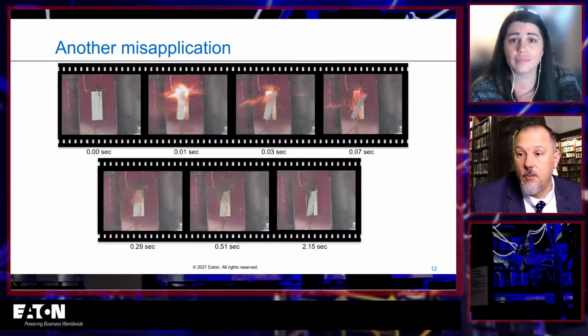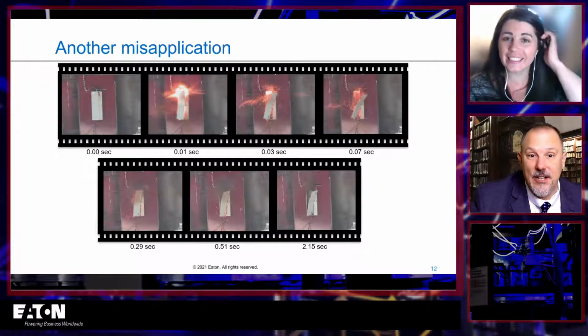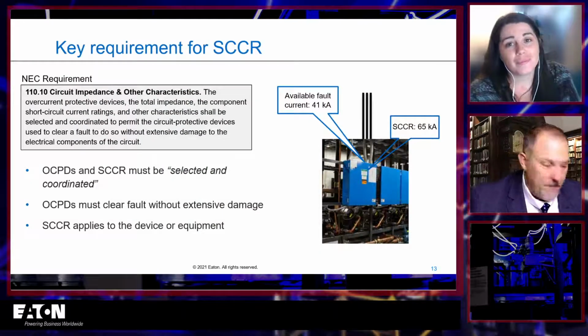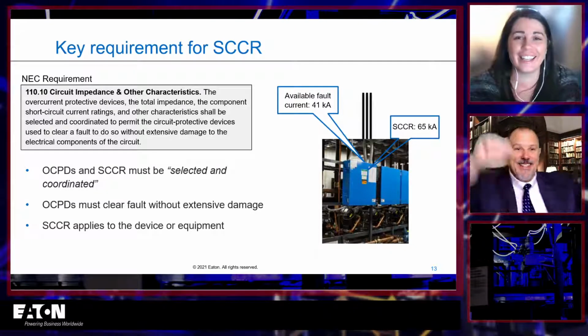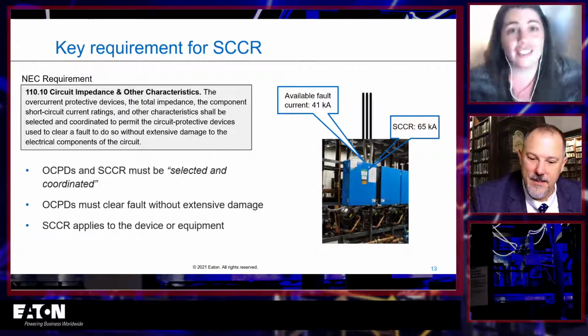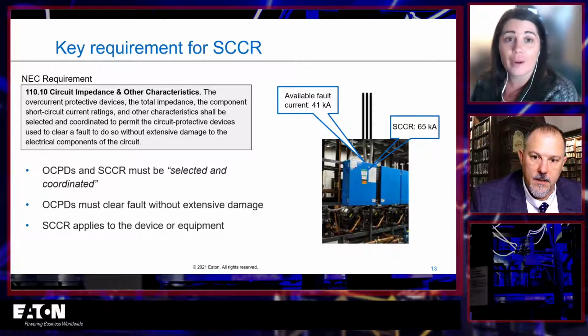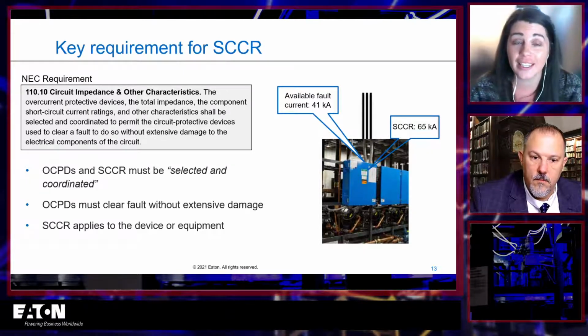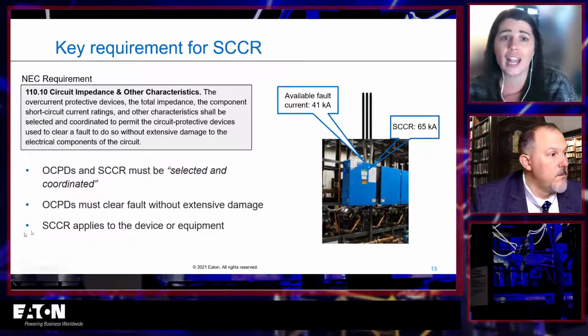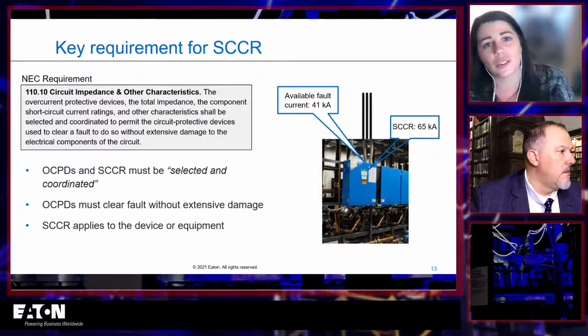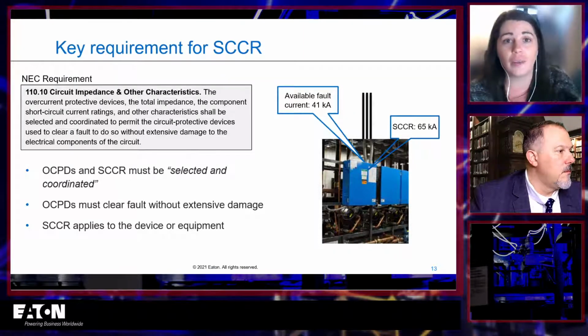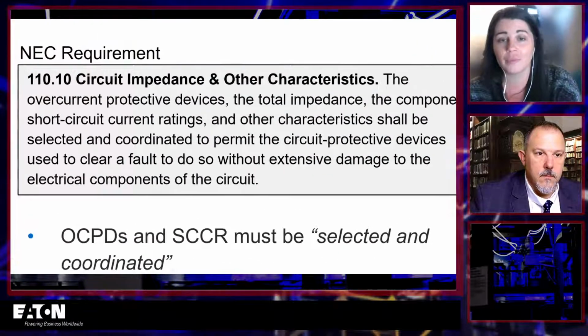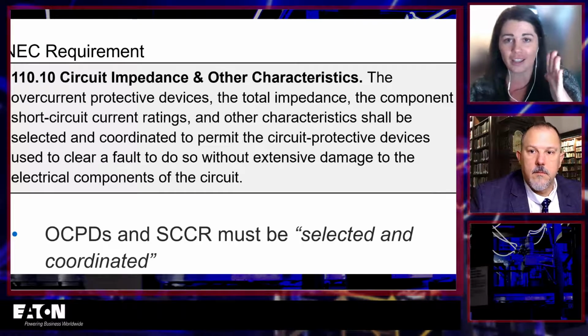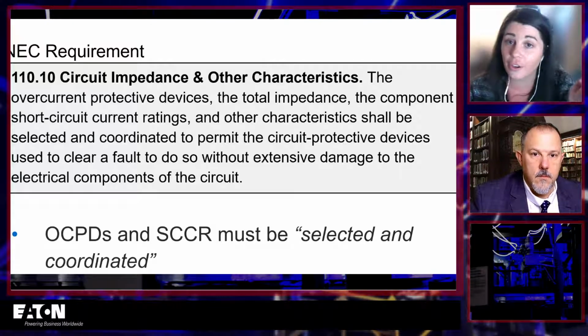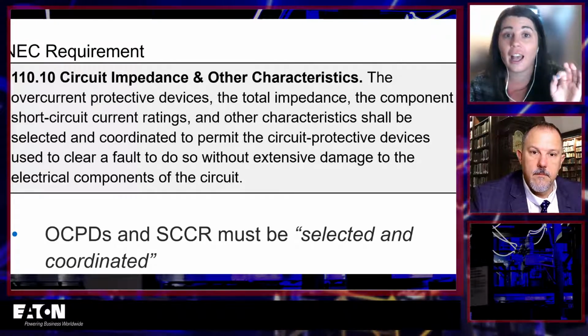And Sharish, Christy is going to be covering how to address the SCCR inside of a panel. So good questions. Hey, look, we finally got to 110.10. So 110.10 is really the overarching requirement for SCCR. Now, SCCR is not actually mentioned in 110.10, but it does say short circuit current rating for all of your overcurrent protective devices. It should all line up so that you don't get extensive damage to your system. To not have extensive damage, your short circuit current rating has to be greater than or equal to the available fault current. That's how we achieve that.